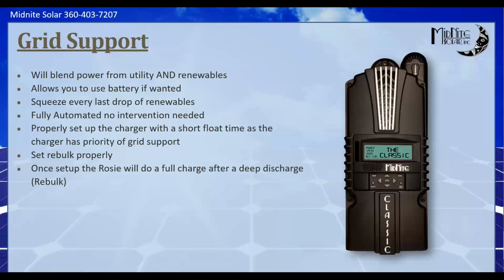And you have to remember that the charger takes priority over grid support. So in this mode, grid support is secondary to your battery charger. So if you had a set of lead acid batteries and you wanted to make sure that they got full every now and then, you could set up grid support to drain the battery to like 50%, and you could set rebulk to like 40%, for example. And then when the battery dipped down to 40% through the night or on a couple of cloudy days, that would force another full charge. It would actually do that 3-stage charge on the battery, then go back into grid support, whereas LBX will actually disconnect, as we'll show you in a little bit later.